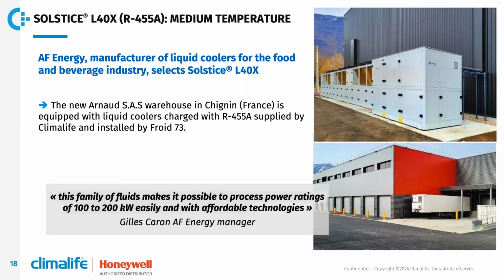The third example, here we have a warehouse to maintain the temperature between 4 and 8 degrees C, and to provide the cooling for the condensing unit using CO2 for low temperature. To meet these needs, three chillers with R455A have been installed. And as Mr. Gilles Caron reminds us, this family of fluids makes it possible to process power ranging from 100 kilowatt to 200 kilowatt cooling capacity easily and with affordable technologies.